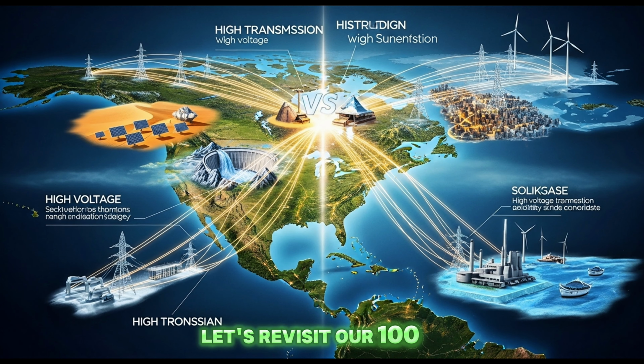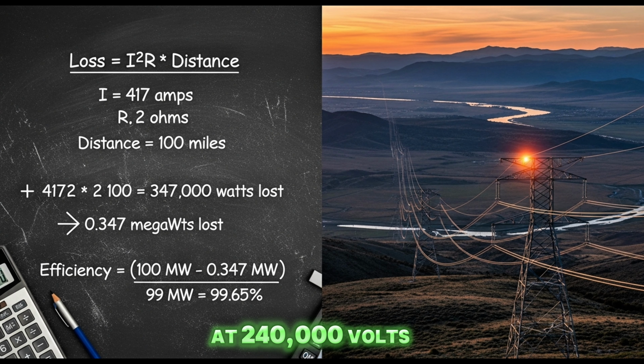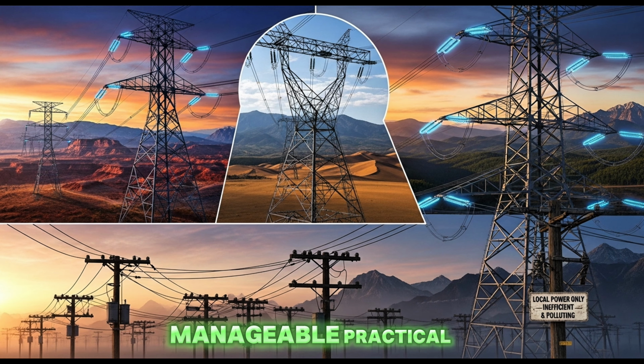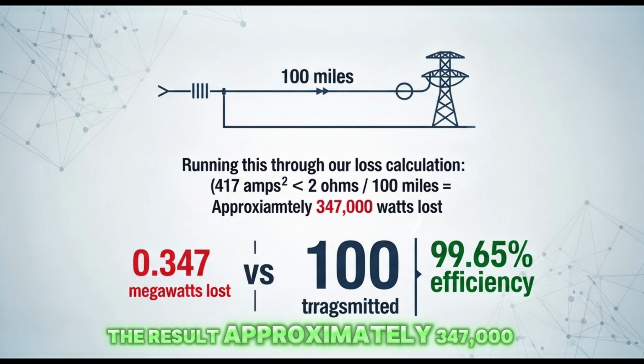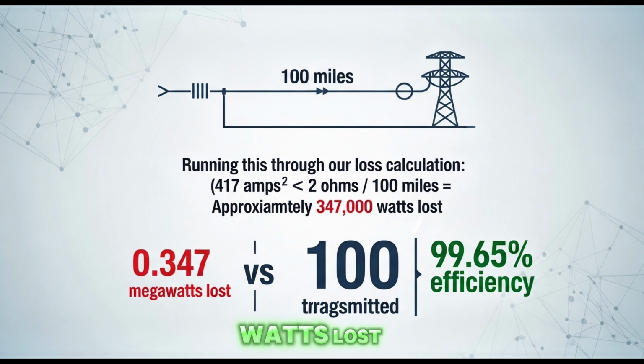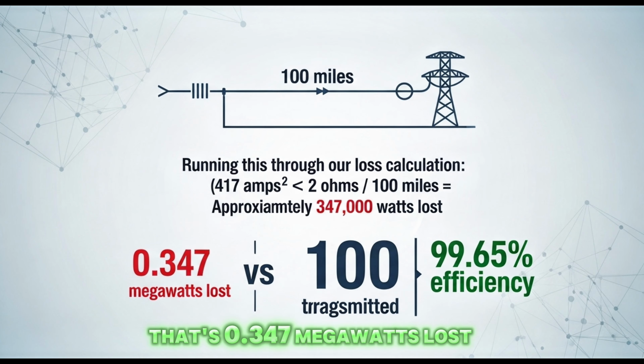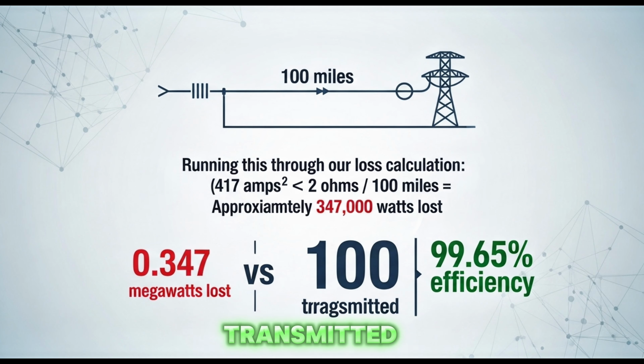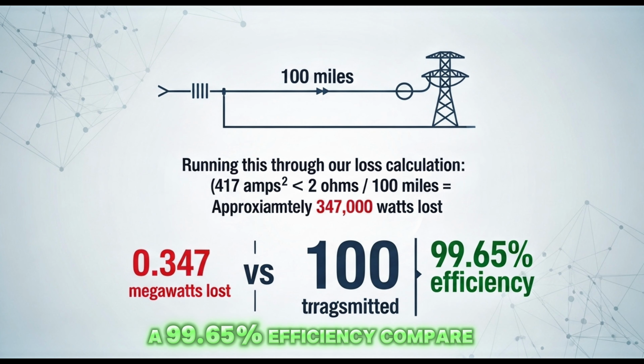Let's revisit our 100 megawatt example, but this time transmitting at 240,000 volts, 1,000 times our original voltage. Now our current is 100 million watts divided by 240,000 volts, which equals 417 amps. Manageable, practical. Running this through our loss calculation, 417 amps squared multiplied by 2 ohms of resistance over 100 miles, the result is approximately 347,000 watts lost. That's 0.347 megawatts lost out of 100 megawatts transmitted, a 99.65% efficiency.